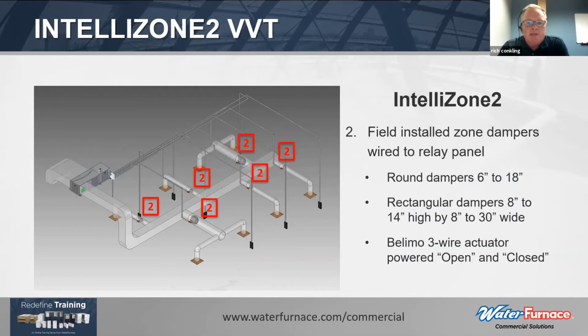Secondly, the zone dampers themselves, you'll see them outlined here on the items numbered 2. They're available in either round dampers, 6 to 18 inches, and rectangular dampers. The construction of the dampers themselves are a heavy gauge galvanized steel, low leakage dampers with seals. They'll withstand up to 1 inch of external static pressure, and the actuators are a Belimo 3-wire powered open and close.